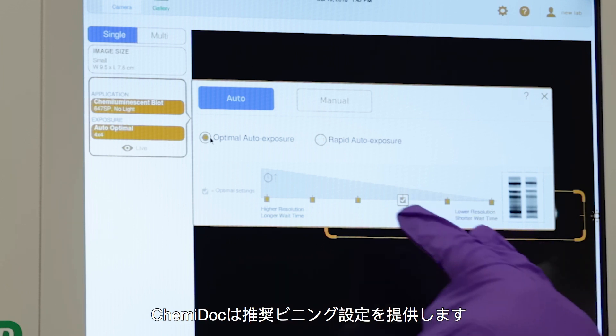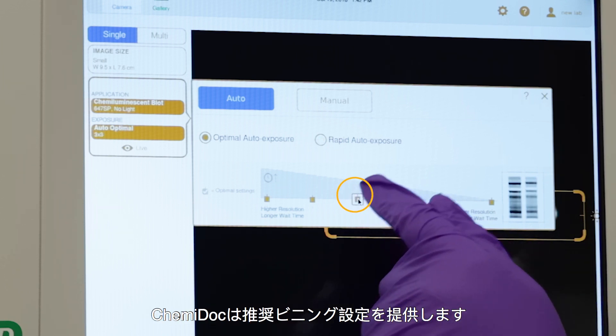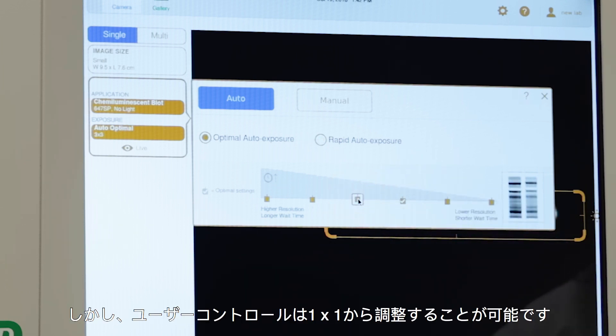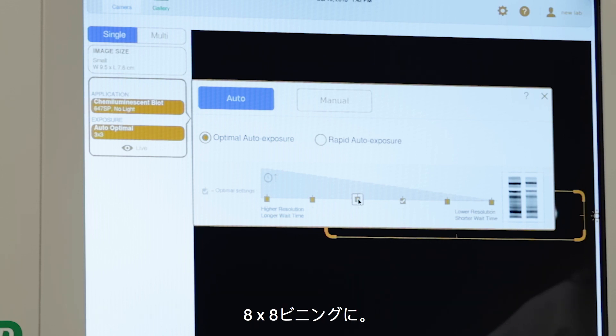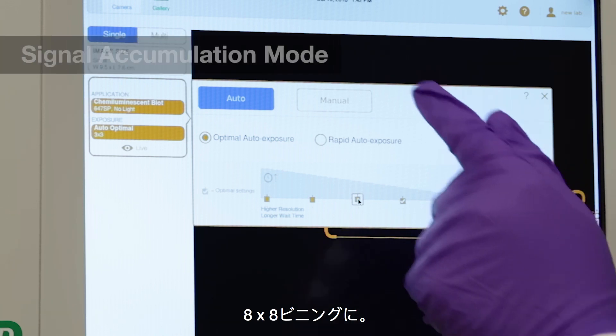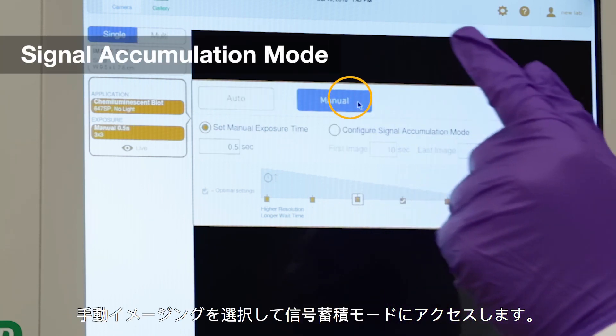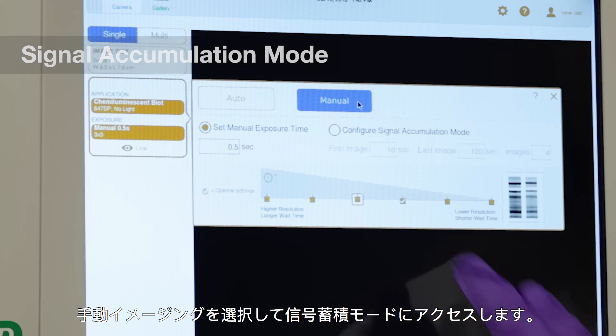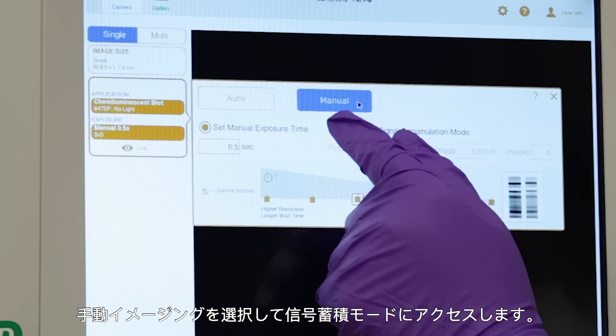The ChemiDoc provides a recommended binning setting for each image, but user control is enabled to adjust from 1x1 to 8x8 binning. Select manual imaging to access signal accumulation mode.